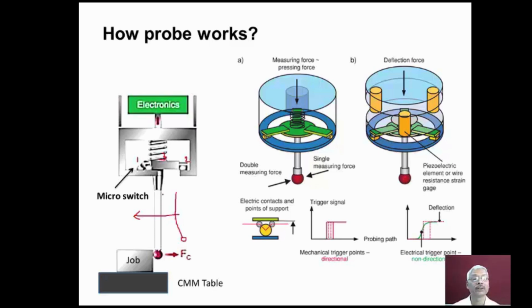Now when the stylus deflects, the micro switch gets opened, and then a signal is sent to the CMM software. So this is a mechanical probe wherein micro switches are used, and then we have another type wherein a piezoelectric element or wire strain gauges are used to sense the contact of the stylus tip with the job.